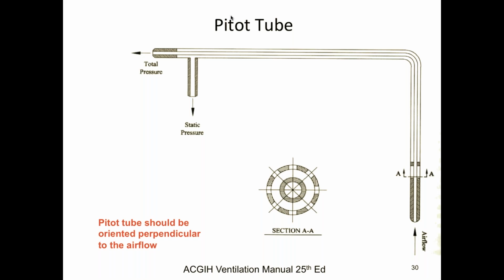When I turn this thing on, I'm not going to turn it on and make noise. When I turn this thing on, air is going to start moving through here. It's moving through here because this fan is producing a suction, right? If I turn the fan on and I cover this entrance to this ductwork, there's still a negative pressure in here. It wants to suck air in. And as you can imagine, if you've ever put your hands over a vacuum cleaner hose, it can suck pretty hard. When you have your hand over it, that suction is potential energy. That suction is energy that can be turned into, when you take your hand away, the moving air. That's kinetic energy. When something's moving, that's kinetic energy. When something has the potential to make something move, that's potential energy.